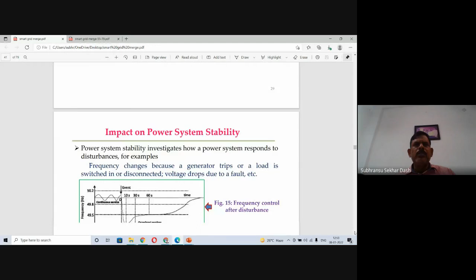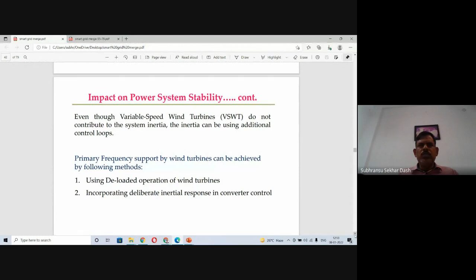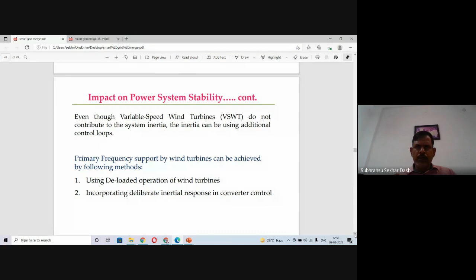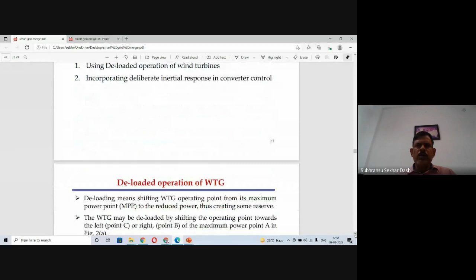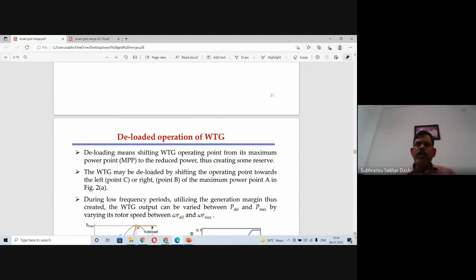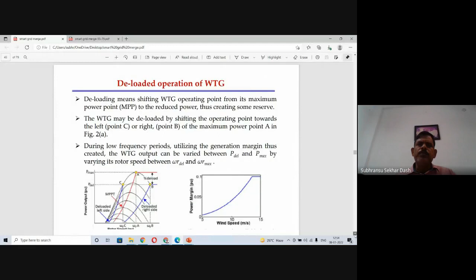Due to this effect, equipment basically gets damaged. Power system stability is a very important and big area. Even though variable speed wind turbines do not contribute to the system's inertia, inertia can be provided using additional control loops. Primary frequency support by wind turbines can be achieved using deloaded operations, which basically means shifting the wind turbine generator's operating point from the maximum power point to a reduced power, thus creating some reserve.